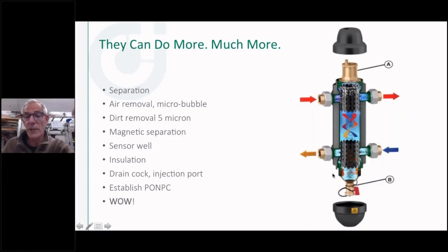Then most recently, we added a magnetic band on the bottom of this. So if you've got any tiny particles, even smaller than 5 microns, which you'll see when we do the demo here at the end, this magnet will pull those out. So now I've got air separation, I've got dirt separation, I've got magnetic separation, and the first thing I wanted, I've got hydraulic separation by the size of the chamber and my closely spaced tees, so to speak, on the side of it.